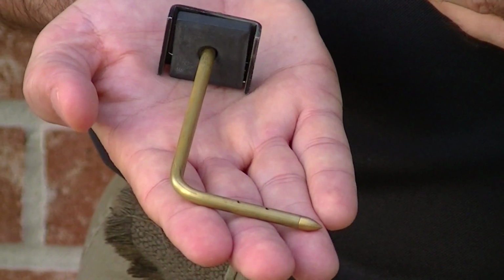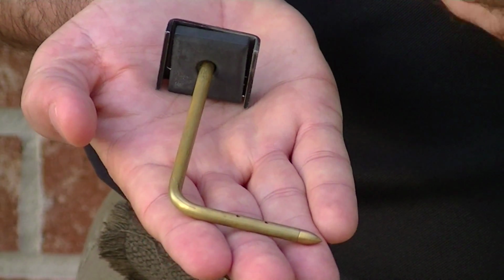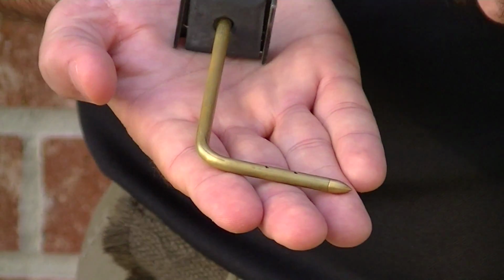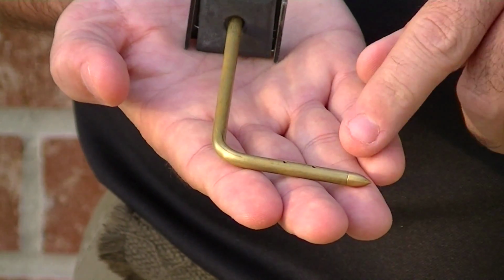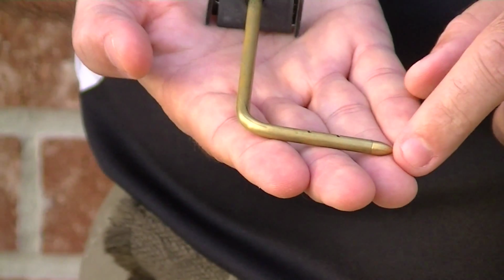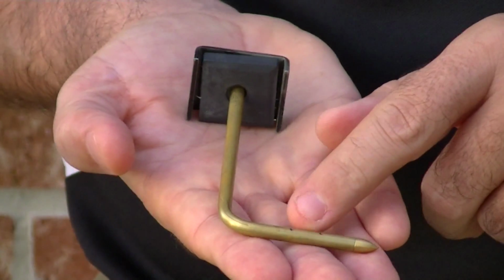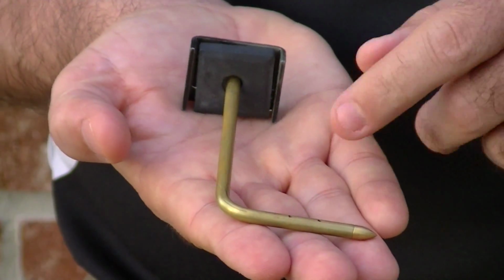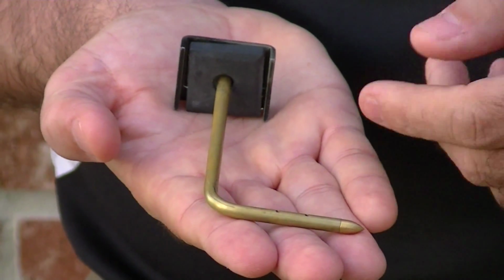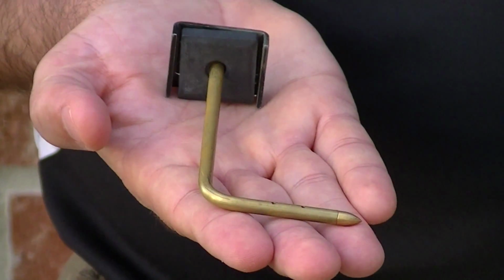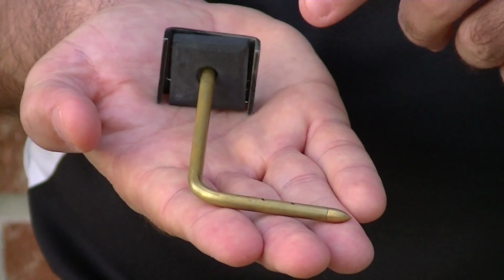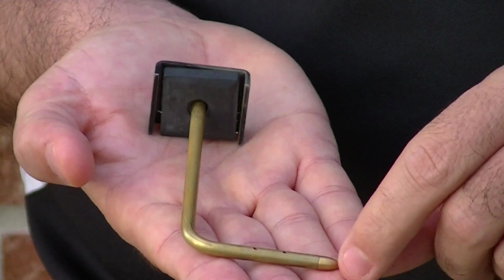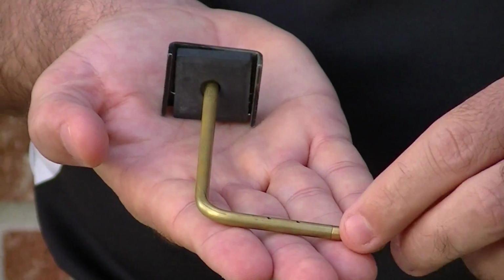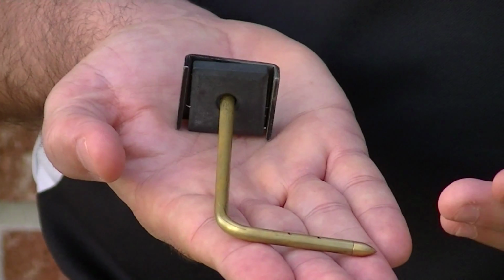This is the static pressure Pitot tube that we use to measure static pressures. This Pitot tube has a tip that's solid, and it's got these little holes on the side right here that will measure the static pressure. It's got holes on the other side as well. Now the best practice is to insert this into the supply plenum and the return plenum, and then orient it so that this tip, while it's covered and it's solid, is pointed in the direction of the airflow.